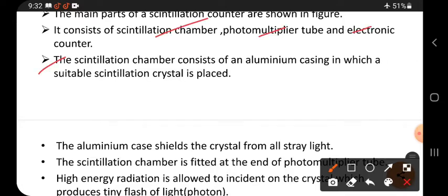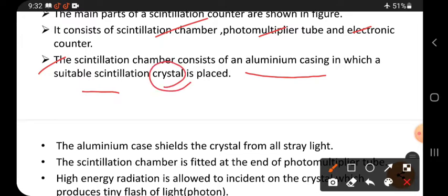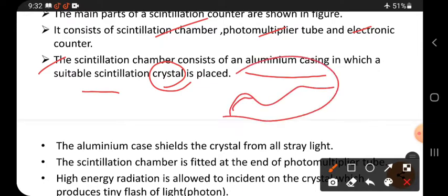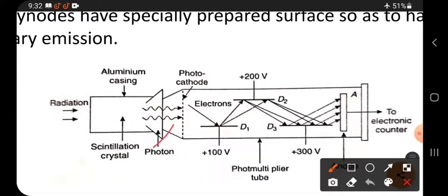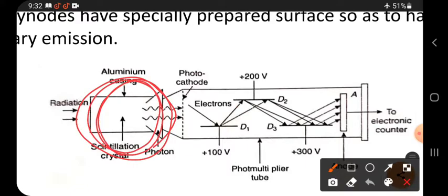The scintillation chamber consists of an aluminum casing in which a suitable scintillation crystal is placed. By using this crystal, we can produce a flash or photons. The aluminum casing contains the crystal, and the flashes — the photons — are produced inside it.